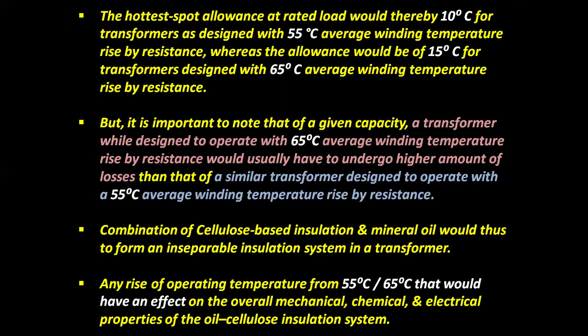The hottest spot allowance at rated load would be 10 degrees centigrade for transformers designed with 55 degrees centigrade average winding temperature rise by resistance, whereas that allowance would be 15 degrees centigrade for transformers designed with 65 degrees centigrade average winding temperature rise by resistance. But it is important to note that, of a given capacity, a transformer designed to operate with 65 degrees centigrade average winding temperature rise by resistance would usually undergo a higher amount of losses than a similar transformer designed to operate with 55 degrees centigrade average winding temperature rise by resistance.